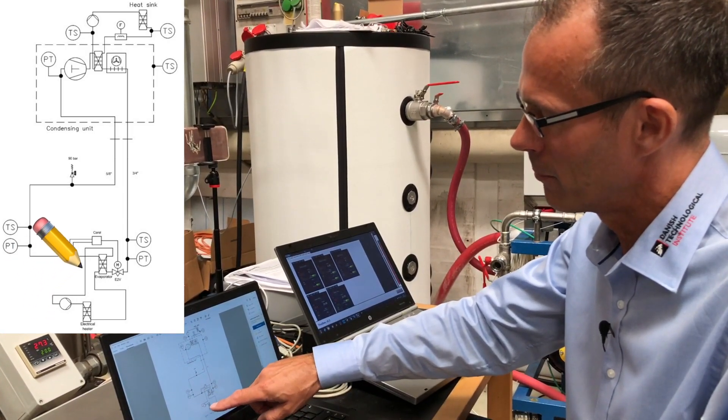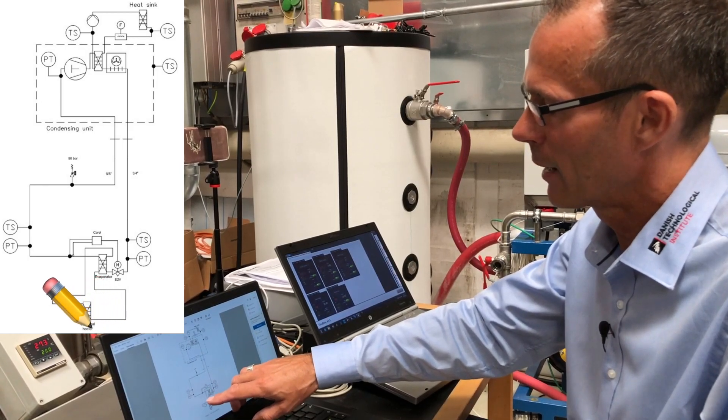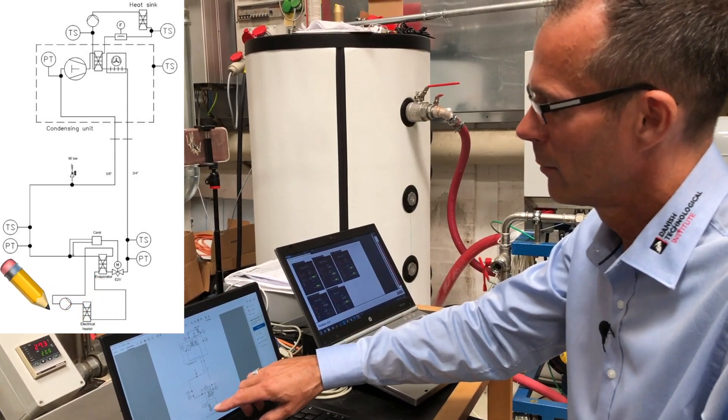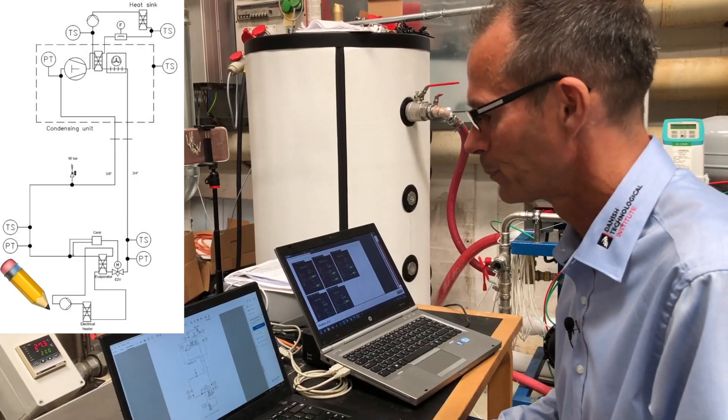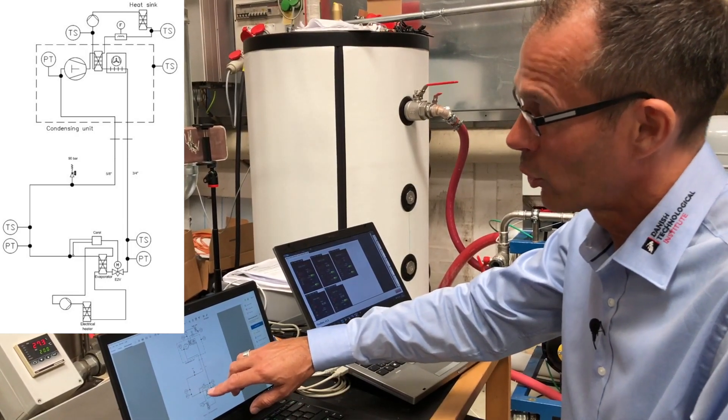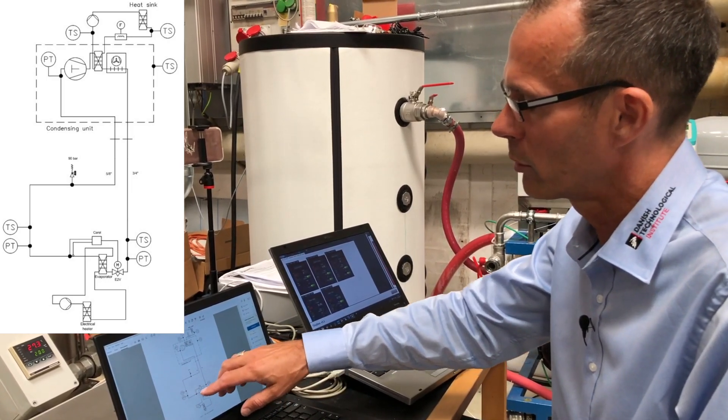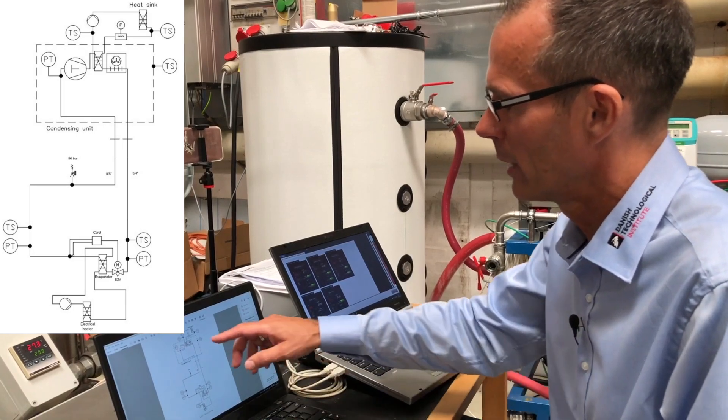The auxiliary heat for this is made by a heating element that we are heating up the glycol that is circulated through this evaporator. The evaporator is a coaxial evaporator to ensure good oil return back to the condensing unit.